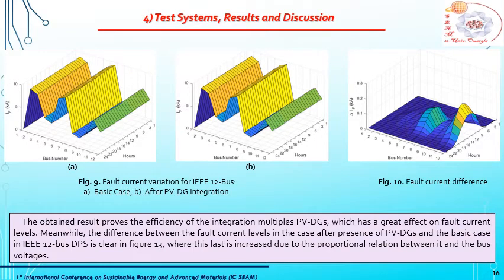In Figure 9 is mentioned the fault current variation for the first test system for cases before and after the integration of PVDG. Also, the difference between them is mentioned in Figure 10. The obtained results prove that the integration of multiple photovoltaic distributed generation has a great effect on the fault current levels, where the latter is increased due to the proportional relation between it and the bus voltage.